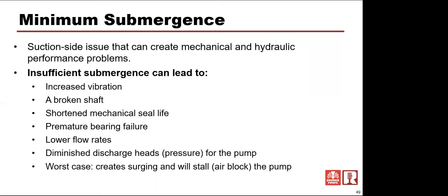So if you go to a larger pipe on an intake side, even though it's only a 3x4/8 pump, if you put a 10-inch pipe, the velocity goes way down in that 10-inch suction pipe, and therefore you can go down to a lower liquid level in that tank and still not draw air down into that pipe. Hope that makes sense. There are some other cheats that you can work around, but one of the big ones is trying to use a larger pipe.